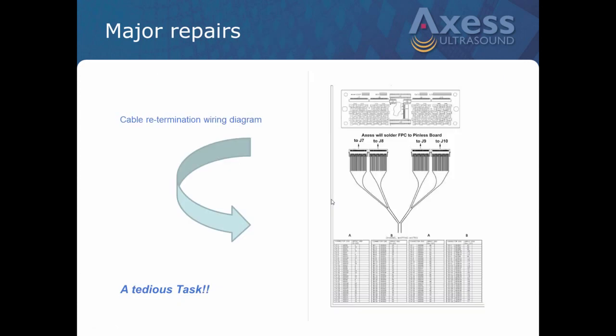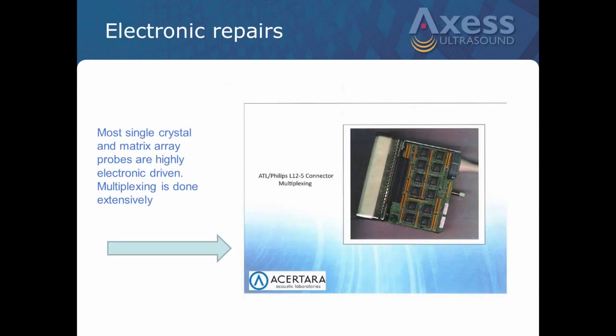You can baseline incoming probes when your hospital buys new equipment. If you have one of these, you can go in and test the probes when they come in with the manufacturer. And then what you will find is probably 20% of the brand new probes you get have some sort of issue, and you can turn right around and tell the OEM you want them replaced immediately. And that's a fact. I've seen it with my own eyes many times, they send you a brand new probe with a brand new machine, and if you thoroughly test it with some of these test devices, it will be bad. But yeah, Brian, it's really dependent on your installed base of probes. If you've got enough, I'd say 100 or above, you'll pay for this. You'll pay for this in no time.